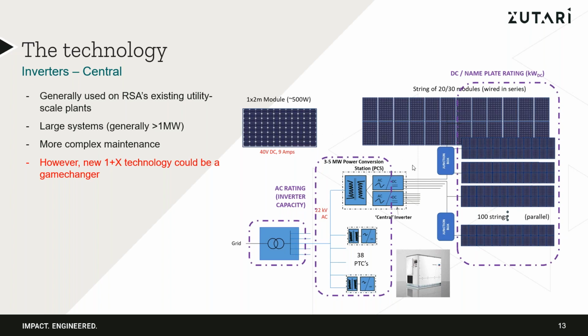In there would be your central inverters, which would sit on one side. You'd have a ring main unit and your MV transformer also within that container, or on skids or plinths nearby. There the inverters would come out as also 400, 800 volts on the other side, then stepping up to the same 22 kV network from there on out. So the MV side out is identical between the two configurations.